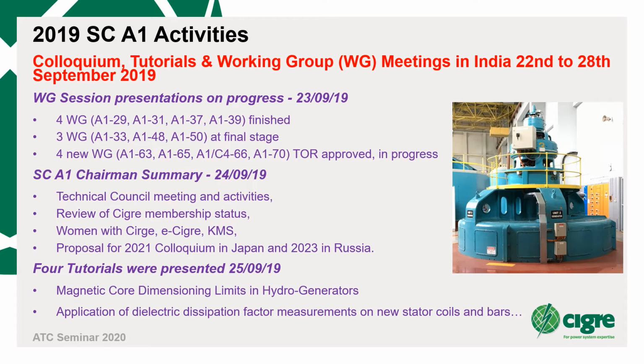Four tutorials were presented: magnetic core dimensioning limits in hydro generators; application of dielectric dissipation factor measurements on new stator coils and bars; guidance on the requirement of high-speed balancing and over-speed testing of turbo generator rotors following maintenance, repairs, or rewind; and guidance on cleanliness and proper storage of generators and components.